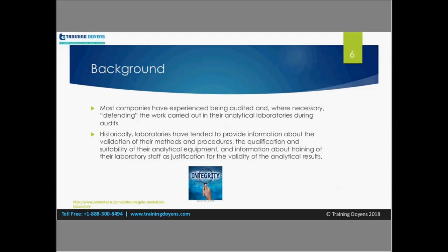Historically, laboratories have tended to provide common information about validation of your methods, your procedures, qualification and suitability of your equipment, making sure that the inspector sees that your staff is trained appropriately, and all of that put together is justification for the validity of your results. And that goes for your operations area as well. You're showing your method is validated, your equipment is qualified, it's calibrated, and your operators are trained.